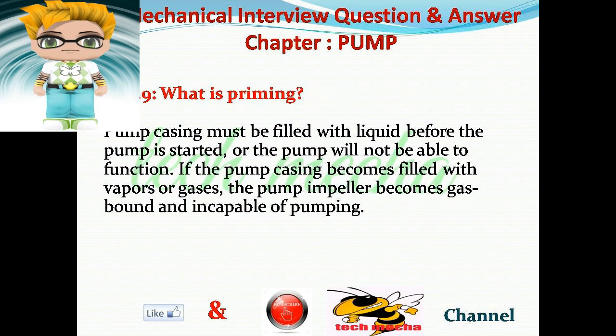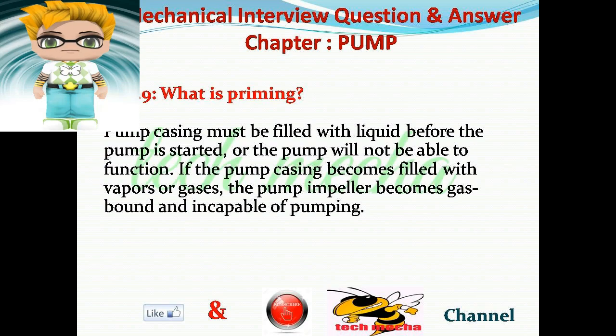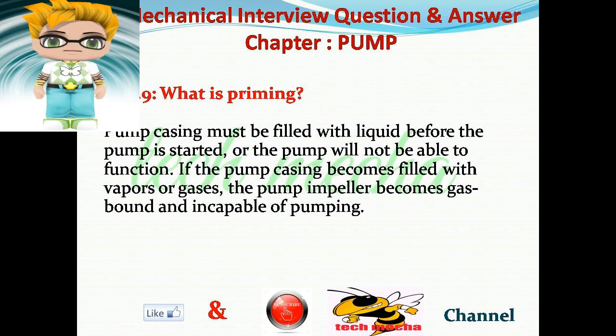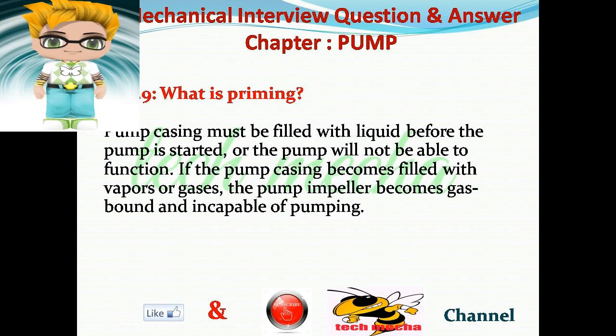Question number 9: What is priming? Answer: The pump casing must be filled with liquid before the pump is started, or the pump will not be able to function. If the pump casing becomes filled with vapors or gases, the pump impeller becomes gas-bound and incapable of pumping.